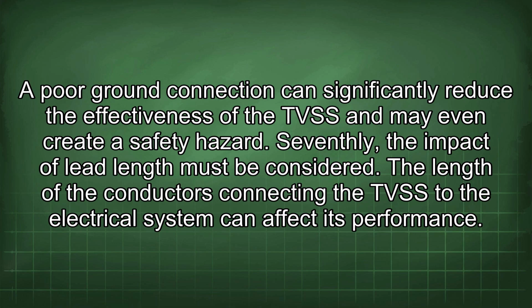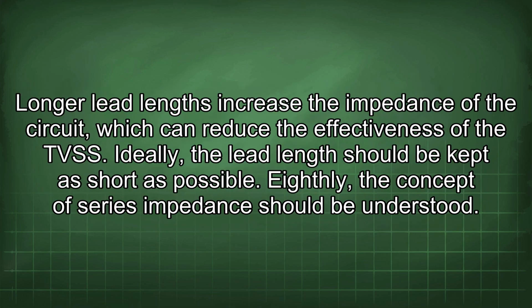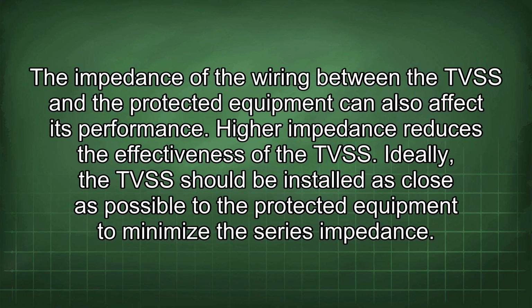The length of the conductors connecting the TVSS to the electrical system can affect its performance. Longer lead lengths increase the impedance of the circuit, which can reduce the effectiveness of the TVSS. Ideally, the lead length should be kept as short as possible. Eighthly, the concept of series impedance should be understood. The impedance of the wiring between the TVSS and the protected equipment can also affect its performance. Higher impedance reduces the effectiveness of the TVSS. Ideally, the TVSS should be installed as close as possible to the protected equipment to minimize the series impedance.